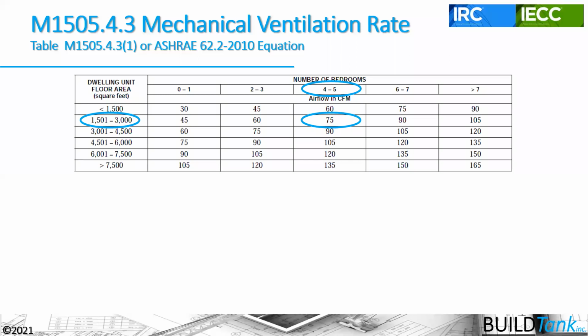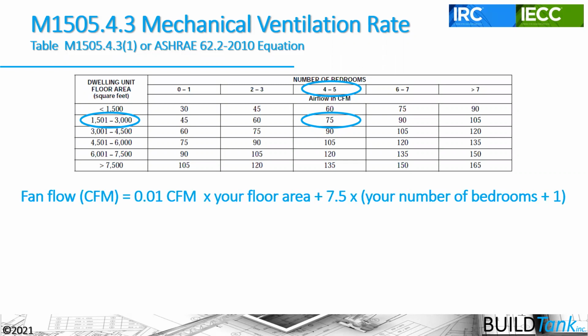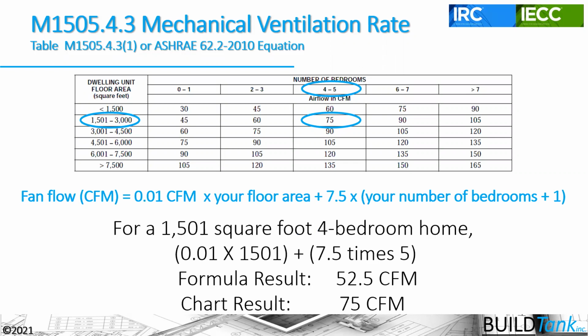So if I have a 1,500 square foot house and it's 4 or 5 bedrooms, I can put 75 CFM of air to ventilate that house with controlled whole house mechanical ventilation. Or I can use this formula to calculate a more specific ventilation rate. The difference between the chart and the formula is about 25 CFM of air. A lot of practitioners, energy modelers or raters, like to be a little bit more specific, so we like to use the formula. But if you're using the prescriptive path of the code, you might just use that chart. Either is okay from a code perspective.